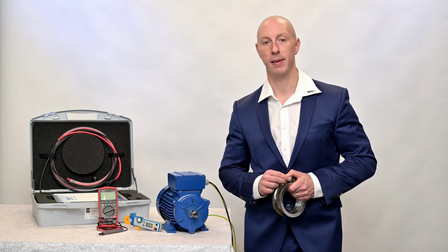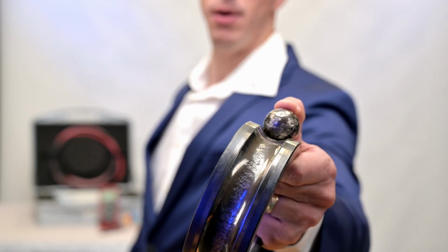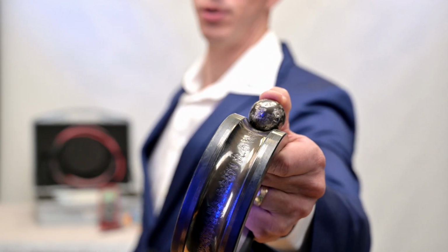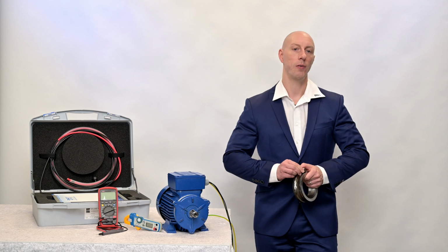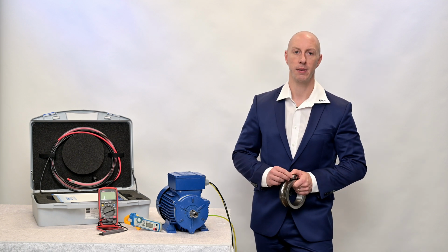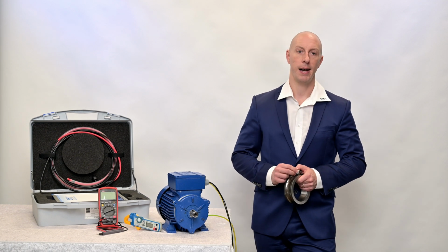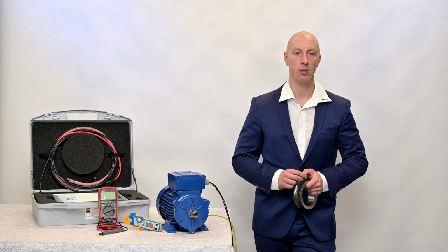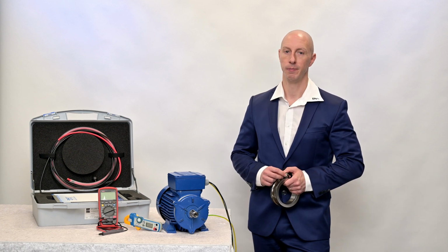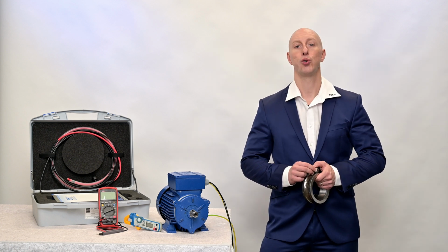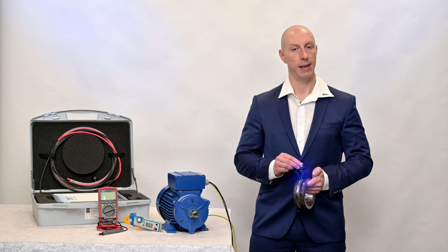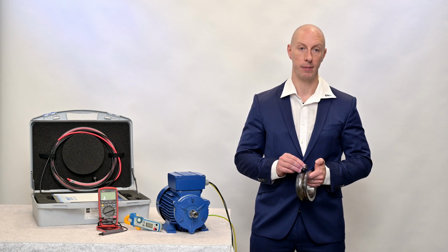With the increasing number of frequency inverter operated motors, bearing damage like this is becoming an increasingly common problem that can lead to failures. Depending on the application, bearing damage can occur after an operating time of several weeks. Even if the damage is so slight at the beginning that it is barely noticeable, the bearing will continue to be damaged as operation progresses, so that the engine can no longer be operated at some point. This is often caused by so-called bearing currents. As the name suggests, these currents flow through the bearing and damage it.